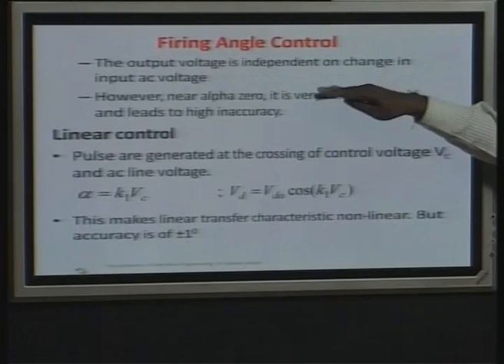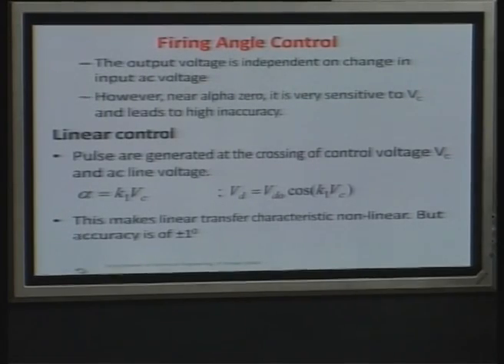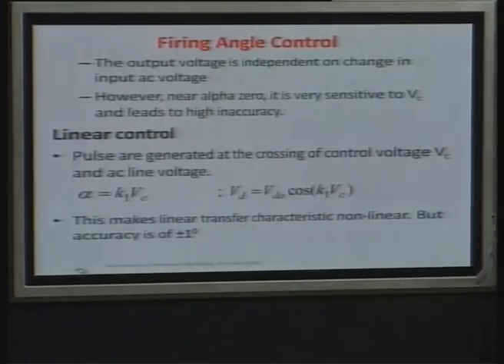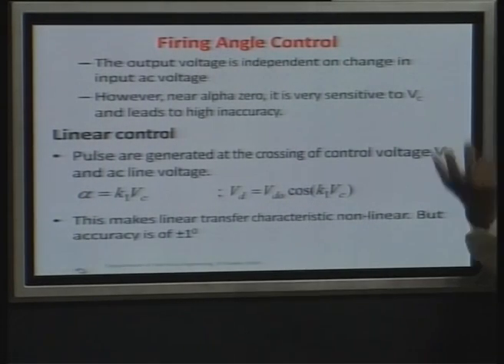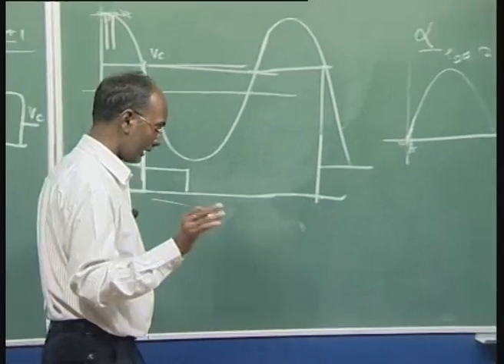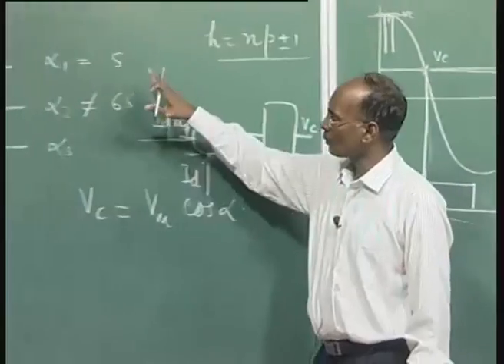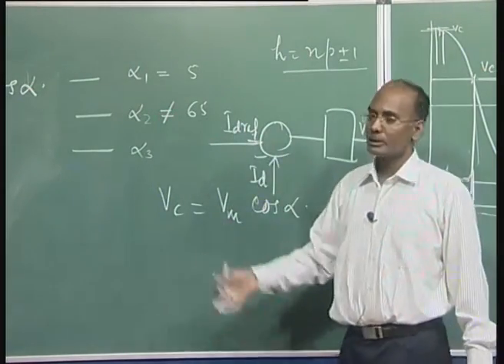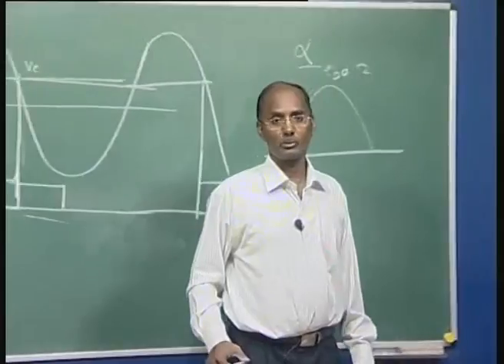In the zone near alpha = 0, sensitivity is very high — even a small error in V_C gives a huge change in degrees. This V_C change gives high inaccuracy, especially when alpha is 0. The linear control has non-linear output voltage but the error is within 1 degree. These two schemes were used in the old mercury arc valve stations and are no longer used, because individual control introduces inter-harmonics and uncharacteristic harmonics, and may even lead to harmonic instability.